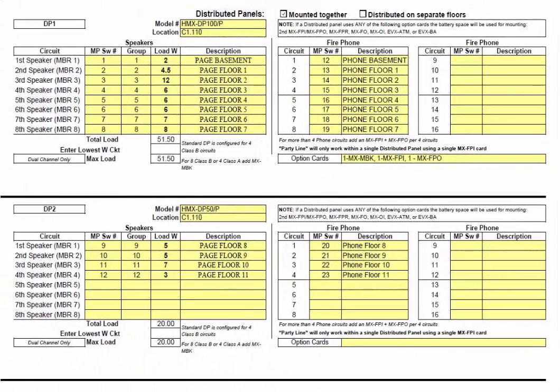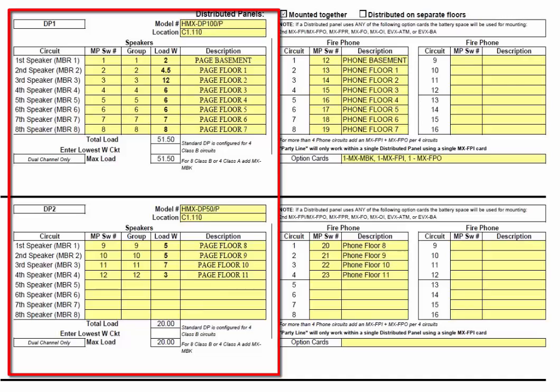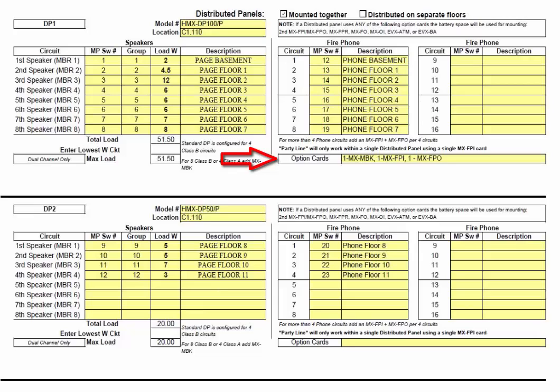Moving forward with the tab labeled Distributed Panel, starting at the top of the sheet, you will choose whether the distributed panels are mounted together or on separate floors. This sheet is divided into two sections: the left side has the Speaker Circuits and the right side has the Fire Fighter Phone Circuits. If you are not using Fire Fighter Phones, you will not need to fill out the right side. Be sure to label the model and location of each Distributed Panel, and map each Speaker Circuit and Phone Circuit to its related Master Panel Switch. Provide a description for each circuit and add up the total for each Speaker Circuit to ensure you are not maxing it out. For any system requiring more than four phone circuits, you will need to add an MX-FPI plus an MX-FPO per additional four phone circuits, entered in the Option Cards line.